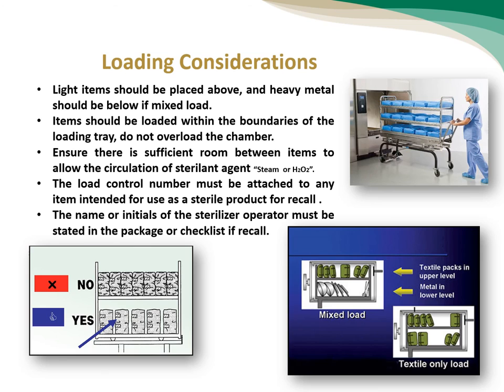Loading of the reusable medical devices. The light items should be placed above and the heavy metal below if mixed loaded. Items should be loaded within the boundaries of the loading tray. Do not overload the chamber. Ensure there is sufficient room between items to allow the circulation of the sterilant. The load control must be attached to any item that will be used as a sterilized product for a recall. The name or initials of the sterilizer operator must be set in the package or checklist for recall.